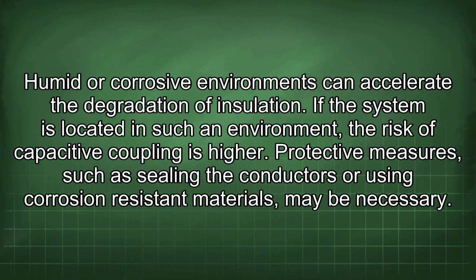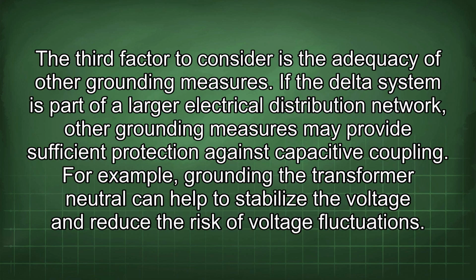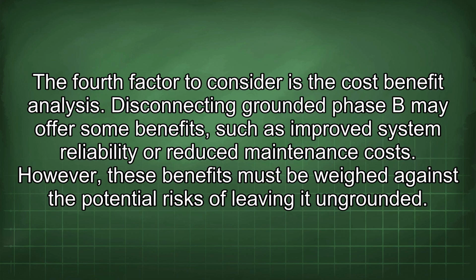Protective measures, such as sealing the conductors or using corrosion-resistant materials, may be necessary. The third factor to consider is the adequacy of other grounding measures. If the delta system is part of a larger electrical distribution network, other grounding measures may provide sufficient protection against capacitive coupling. For example, grounding the transformer neutral can help to stabilize the voltage and reduce the risk of voltage fluctuations. The fourth factor to consider is the cost-benefit analysis.